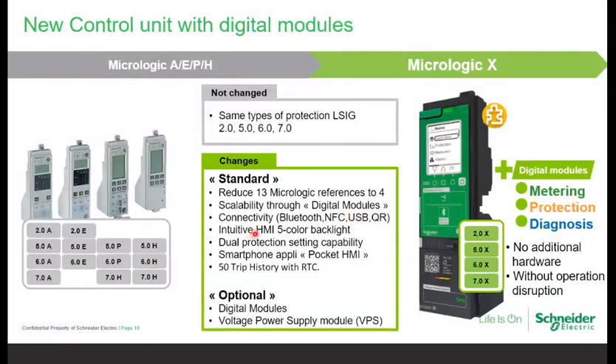Then again, the MTZ trip unit comes with an intuitive 5-color backlight display. So this display comes with a 5 color combination. So what is the use of this? From a distance, from far away, you will come to know, let's say if your trip unit display has turned red, it means from a distance you will understand this particular ACB is under fault. So this is the use of the color backlight display. From a distance also you will come to know whether your breaker is healthy, under warning, or under fault.